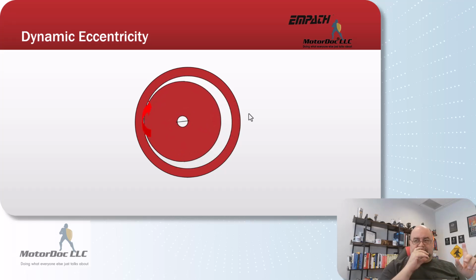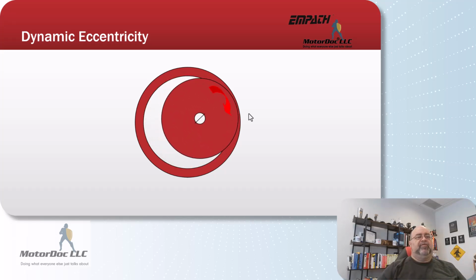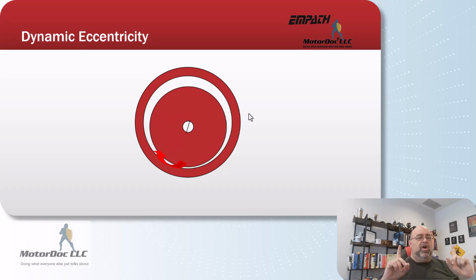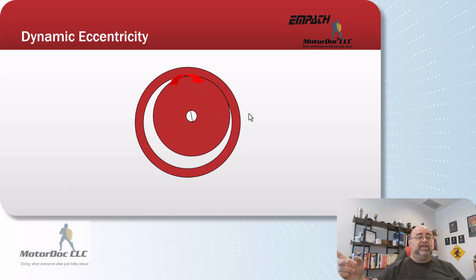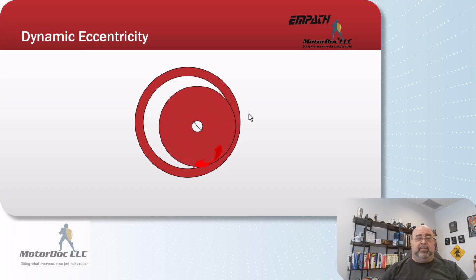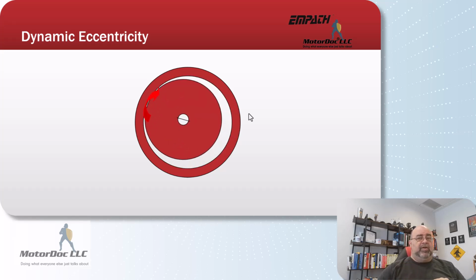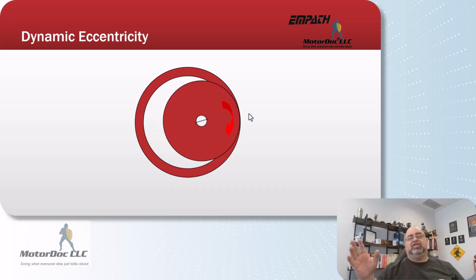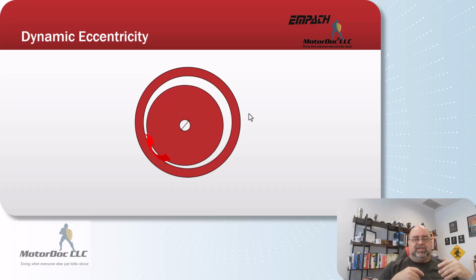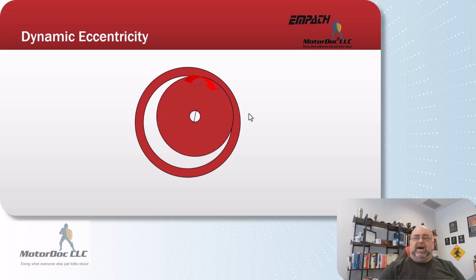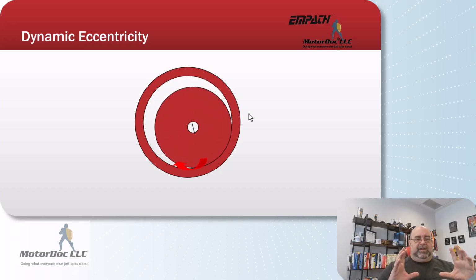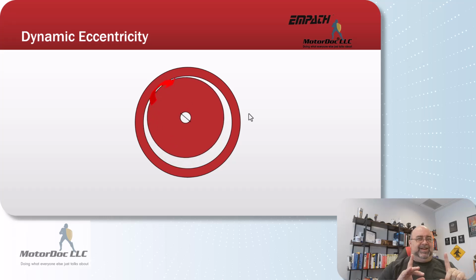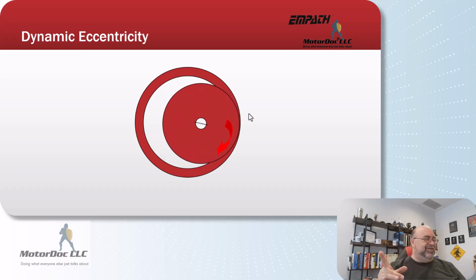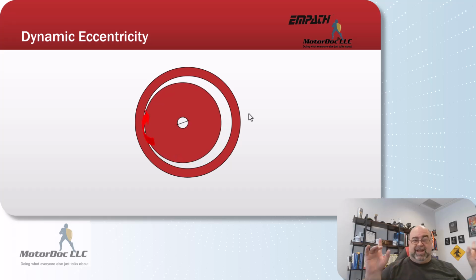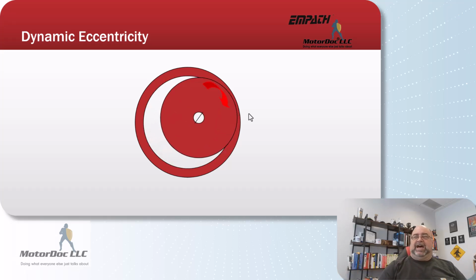Now, the static eccentricity results in the number of rotor bars times the RPM plus and minus 1, 3, and 5 times line frequency. Now, this is the error I had introduced into the paper, into the prior thing, and I'd always meant, I forgot to change this slide when I do my presentation, but it's a deliberate error to catch exactly what happened. So it was not supposed to be line frequency, twice line frequency, and 3 times line frequency. It is 1, 3, and 5. That was very interesting, but neither here nor there.